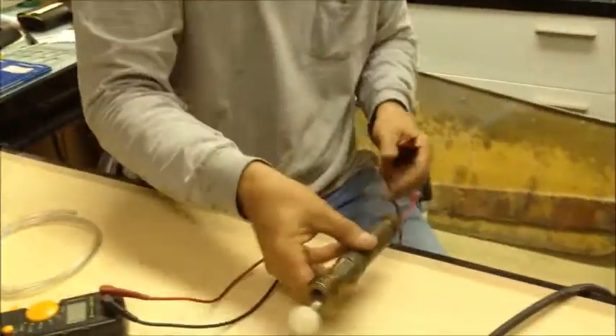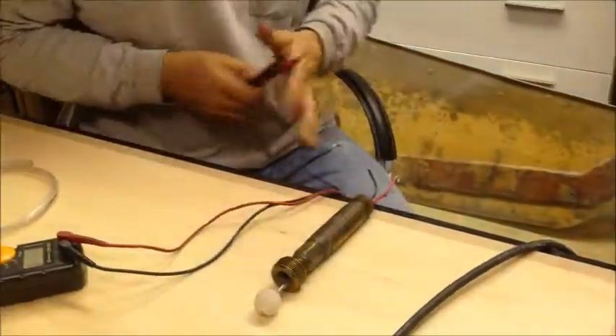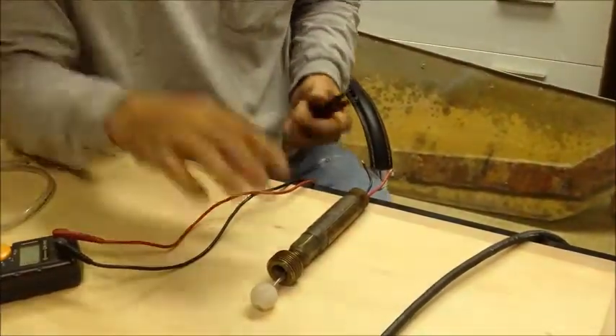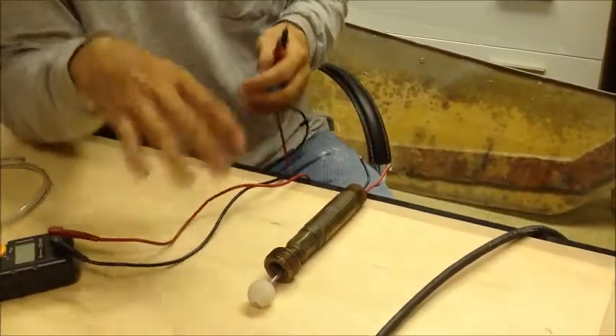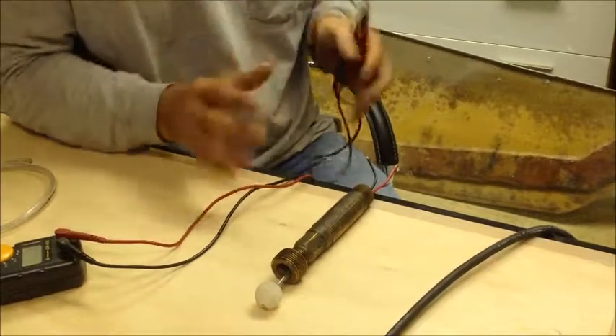The way we want to test these switches to make sure they work is to isolate them from the electrical, which means completely disconnect all the wiring going back to the control panel. All we're interested in doing is checking the switch itself, not anything other than the switch.